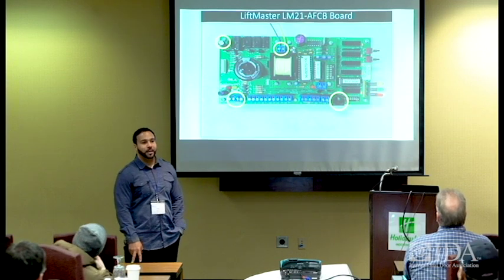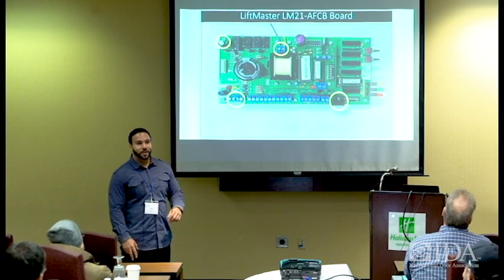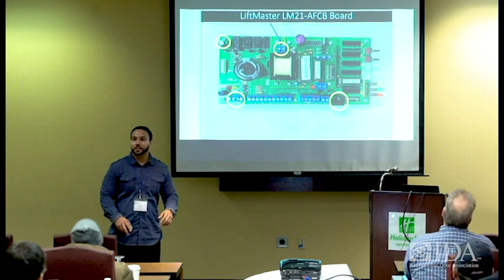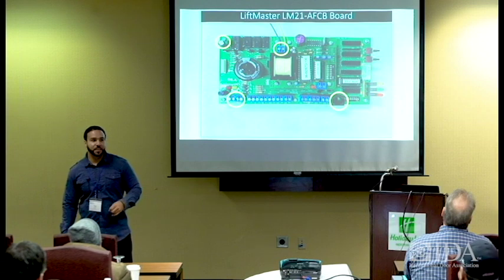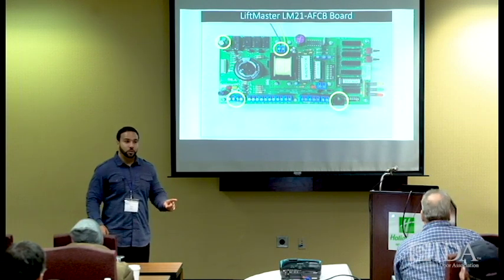And I ask that you not let anybody, or the maintenance man or nobody, go in there and take a screwdriver and pop the piezoid. Because if you do that, you're not going to get the alerts that you need to know when it needs maintenance, know when the batteries need changing, and you're not going to know when it goes into a true alarm if you do not have an annunciator. So this is the key.